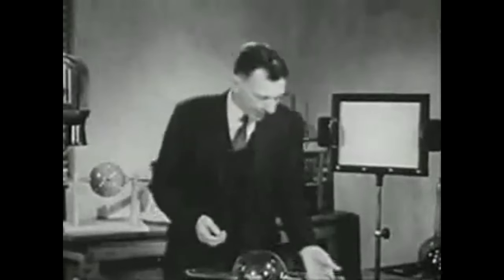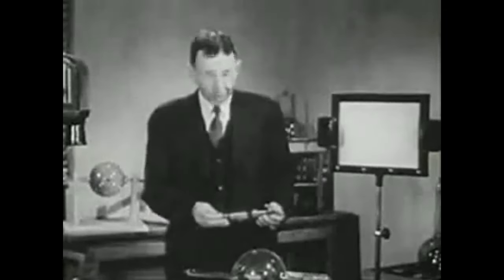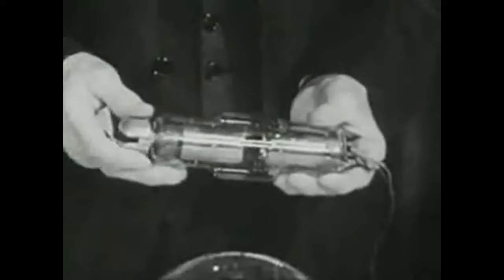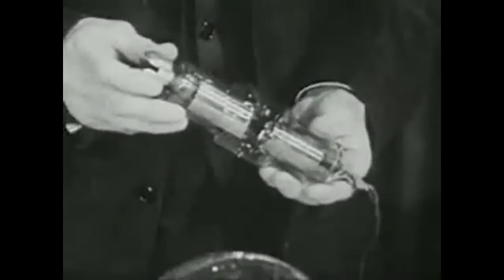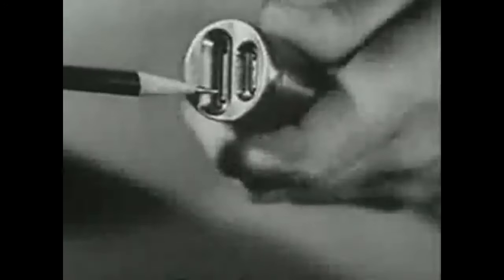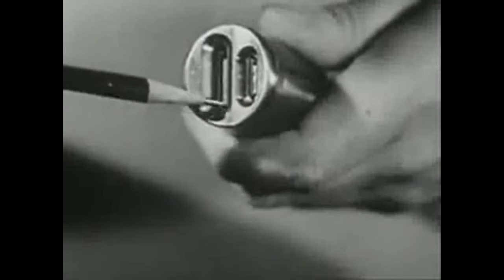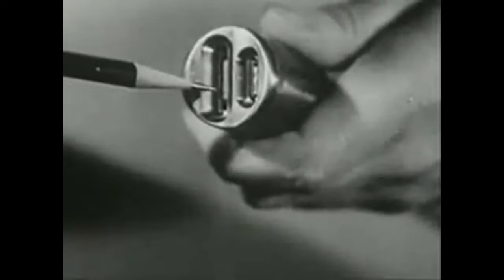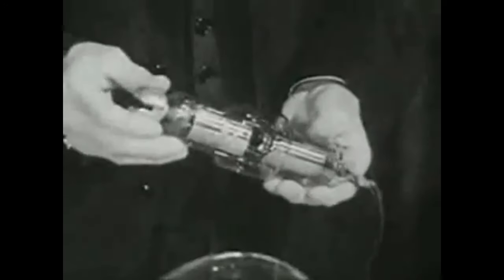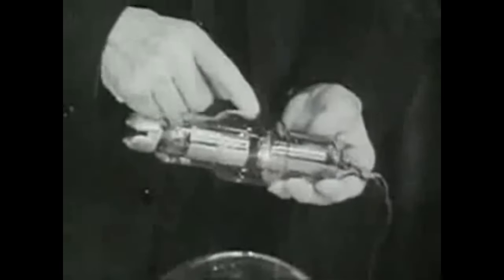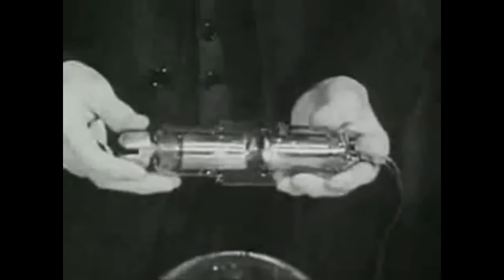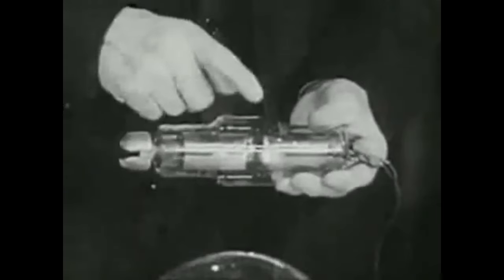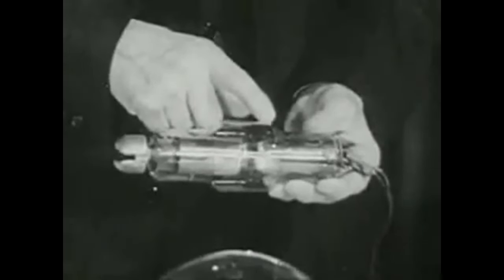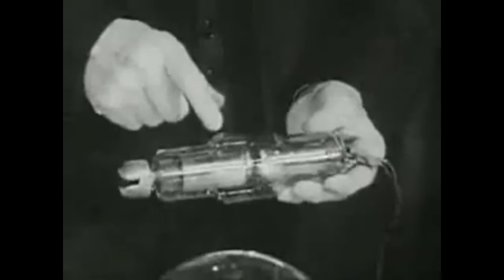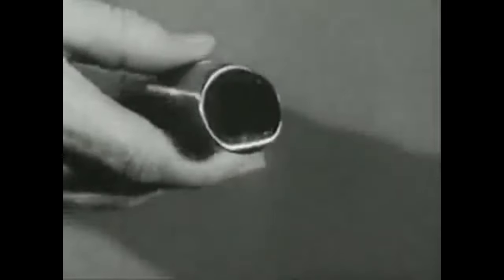In the present day, hot cathode X-ray tube, of which this is one of several different types, there is a high vacuum, and the production of electrons depends only on the size and temperature of an incandescent tungsten filament with a cup-shaped structure surrounding it. This particular tube has two filaments, either of which may be used. The swarm of electrons, which is liberated or boiled off from the white-hot filament, is speeded up to a very high velocity by high voltage applied between the negative electrode or cathode, which carries the filament, and the positive electrode or anode, which is called the target.